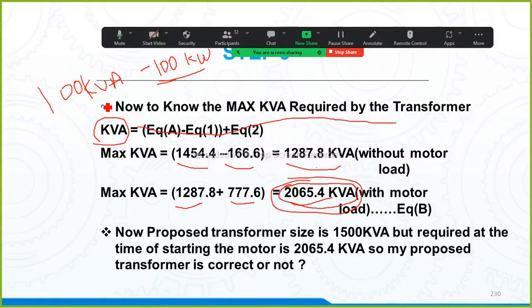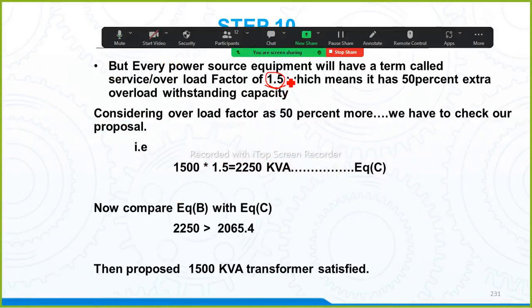Overload test. और overload test का मतलब क्या है? We need to add some 10% or 20% or 30% or 40 or 50% based upon the service factor which has been given. Here the service factor is given as 1.5. इसका मतलब क्या है? We need to add 50% extra or extra overload compared to the existing load. Overload withstanding capacity means 50% extra load which we need to add up.